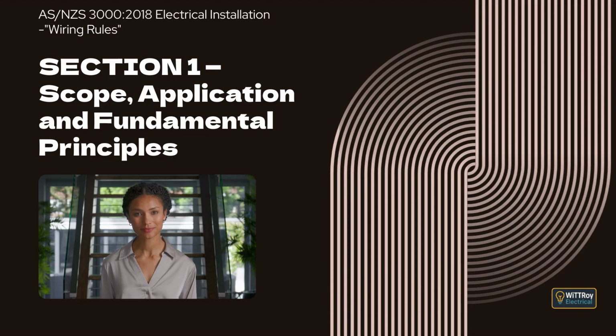Control devices must be arranged so that they do not interfere with the operation of any other equipment, and they must not be affected by other equipment accidentally. An isolation device must be able to disconnect all active conductors, and depending on the situation, may also need to operate in a neutral conductor. This isolation must remove the supply from all external sources. The standard reminds us that a device used for isolation must not interrupt an earthing conductor, or a combined protective earth and neutral conductor. Clause 1.5.3, Protection against electric shock. Clause 1.5.3 covers the key requirement.